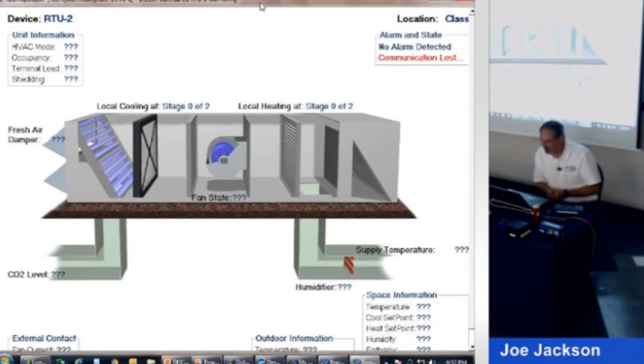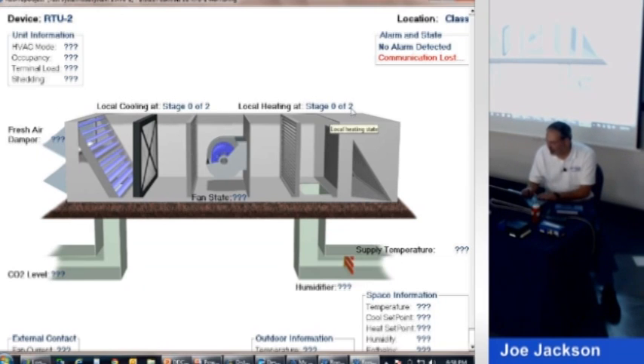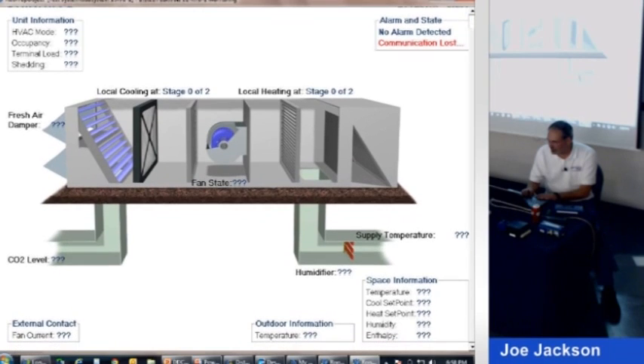So it drew our rooftop unit. Here's our humidifier. Again, if this was live, they wouldn't have question marks. It would be information. We put a humidifier on it. It would tell us if it's on or off. Here's our supply temperature sensor we stuck in it. We put a fan current sensing donut on here. We put a CO2 sensor on it. We have an outside air damper. We have 2 stages of cooling, 2 stages of heat. All of our set points would be here. It would show us the room temperature, the cooling and heating set points, the humidity set point, and the outside air temperature sensor. And all of these things came together in a nice, simple way for us to look at and check out. This is why we like configurable controllers.